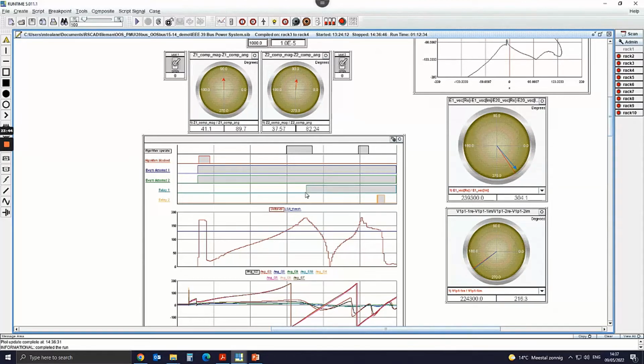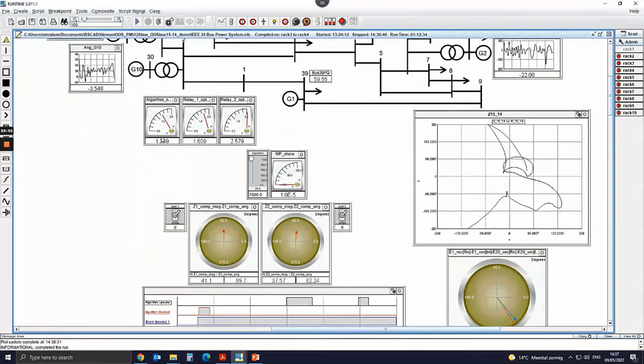relay 1 issues an operation command later than the developed protection algorithm, and relay 2 operates on the second swing in the network. To see the operation times here, the protected line was disconnected from the network by the developed algorithm almost 300 milliseconds faster than relay 1 and 1.2 seconds faster than relay 2. Therefore, the developed protection algorithm offers faster out-of-step condition detection.